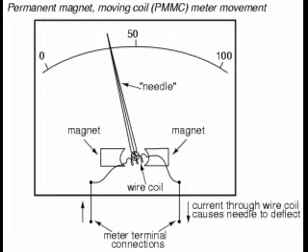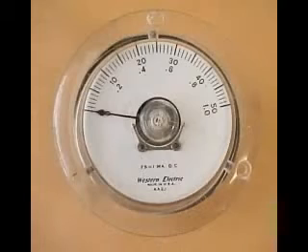The arc on the meter display is labeled with numbers to indicate the value of the quantity being measured, whatever that quantity is. In other words, if it takes 100 µA of current to drive the needle fully to the right, making this a 100 µA full scale movement, the scale would have 0 µA written at the very left and 100 µA at the very right, 50 µA being marked in the middle of the scale.